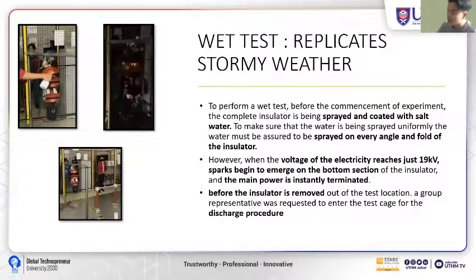Then we proceed to the wet test. The wet test will replicate stormy weather. Before we perform the wet test, the insulator will be sprayed with salt water, and the salt water will be uniformly dispersed around the insulator on every angle and fold of the insulator. Based on the wet test, we achieved 19 kilovolt before the spark emerged at the bottom section of the insulator. And when the spark emerged, the main power was instantly terminated for safety.